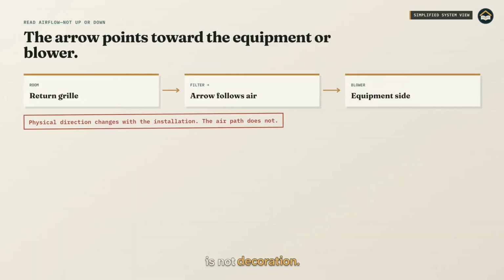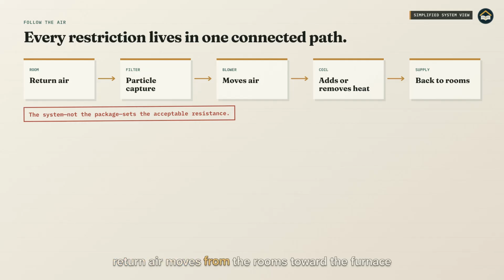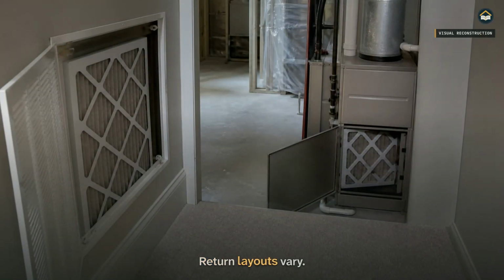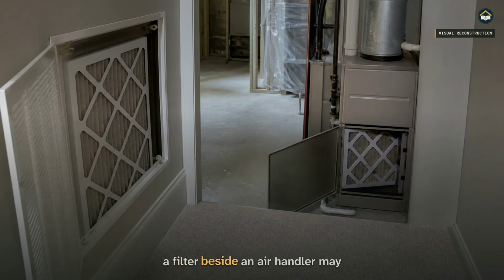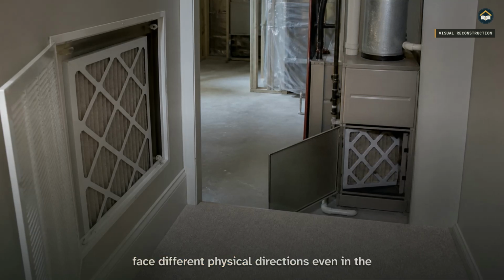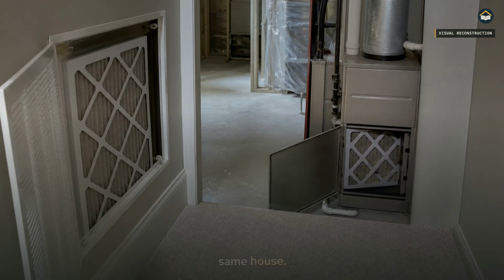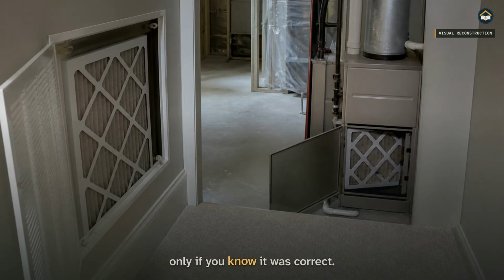That small arrow on the filter frame is not decoration. It marks the direction the air should travel through the media. In most forced air systems, return air moves from the rooms toward the furnace or air handler, then through the blower and condition side of the system. The arrow therefore points toward the equipment or blower, not automatically up, down, left, or toward the room. Return layouts vary. A filter at a wall grill and a filter beside an air handler may face different physical directions even in the same house. Use the arrow on the old filter only if you know it was correct.